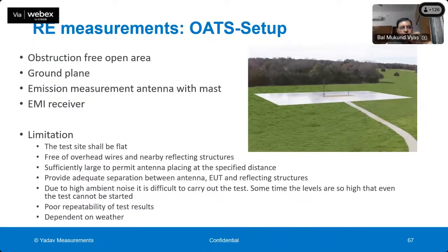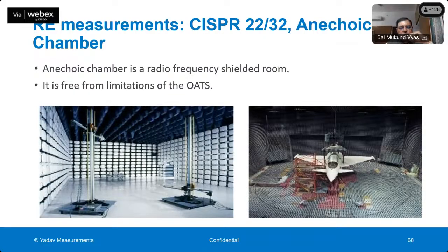One method to do this testing is to use an open area test site, but nowadays it is very difficult, because an open area test site should be at a place without surrounding electromagnetic interference, and nowadays it is very difficult to find such a site because electromagnetic interference is available everywhere. So most of the time this kind of test is done in an anechoic chamber, similar to the anechoic chamber which I explained for the electromagnetic high frequency immunity test. This is an electromagnetic anechoic chamber. Similar to what I have shown, such chambers are used even for testing aeroplanes or fighter planes, right?